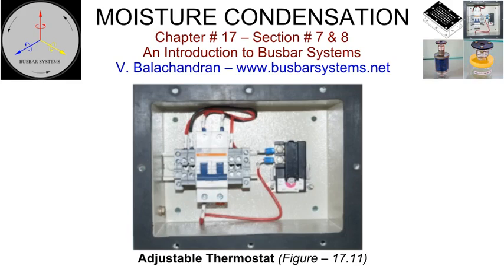The most effective solution combines heaters with control devices like hygrostats, thermostats, or hygrotherms. Thermostats trigger heaters when the temperature falls below a set point. Hygrostats turn the heaters on when humidity rises above a given threshold. Hygrotherms do both. Using hygrostats to control heaters is considered more energy efficient but more expensive. Thermostats seem to be the most popular way of controlling the anti-condensation heaters.